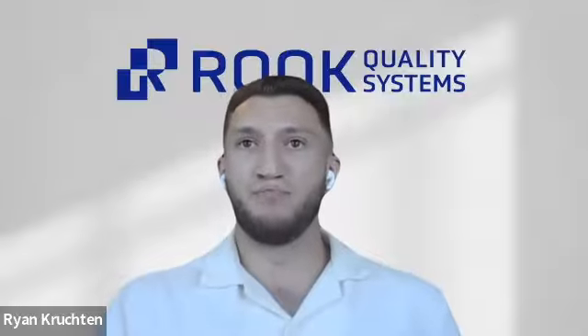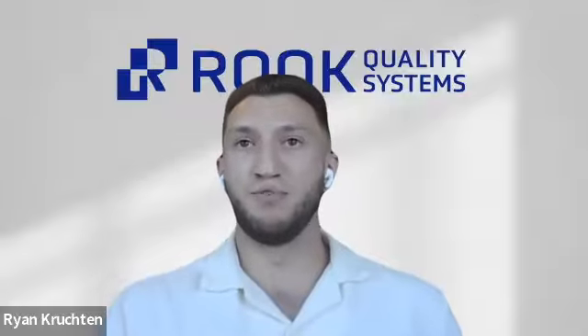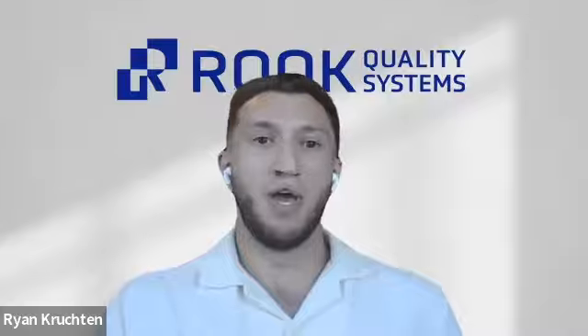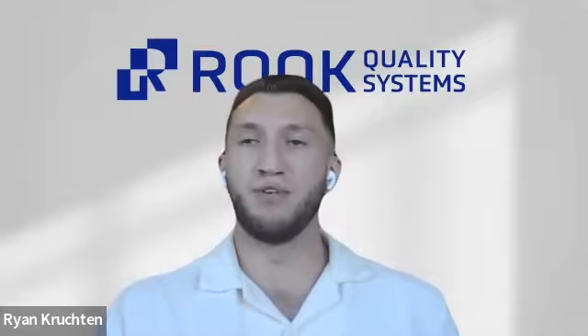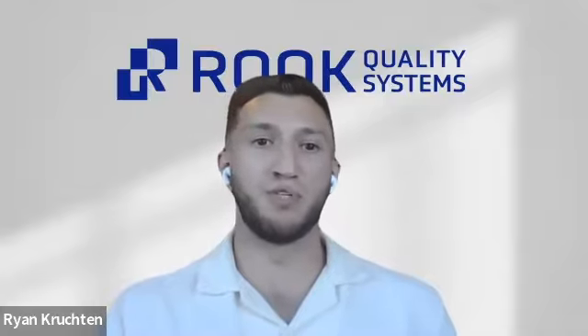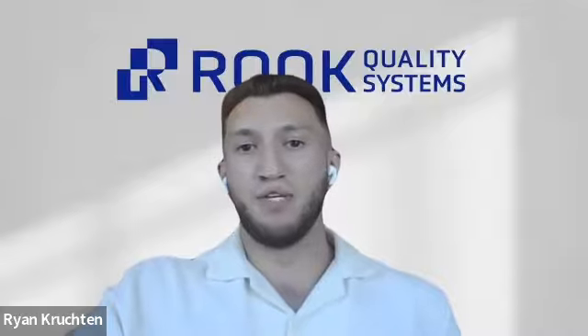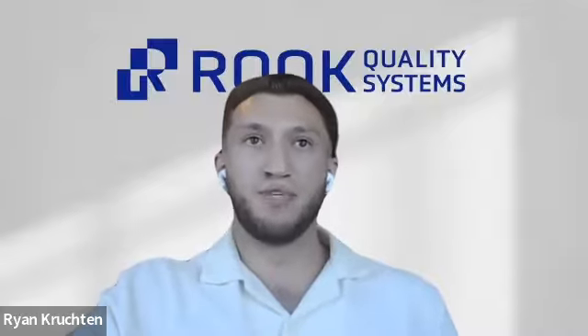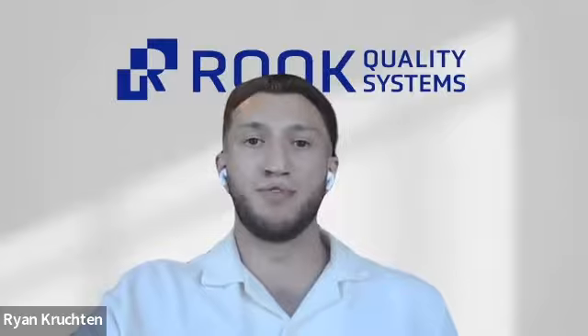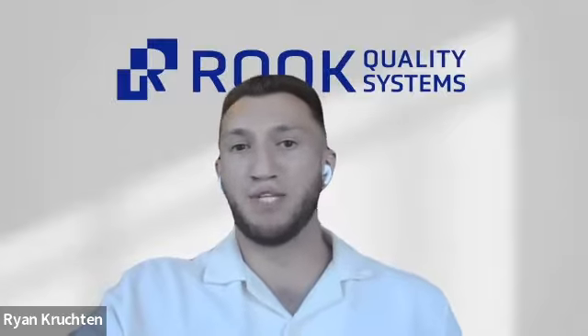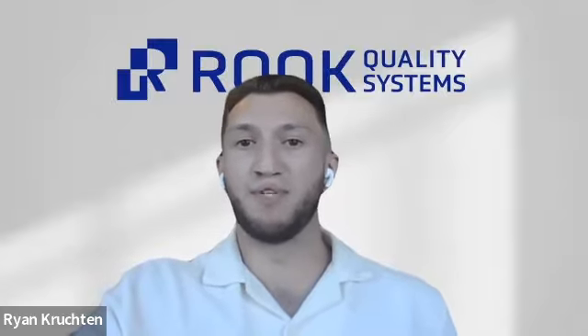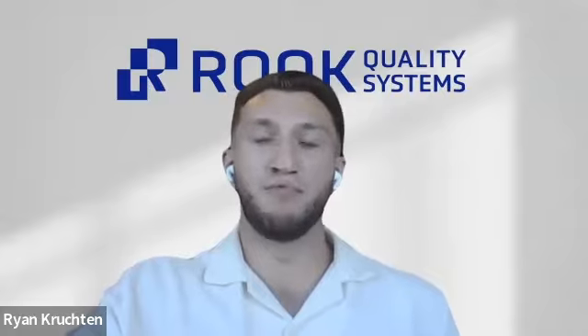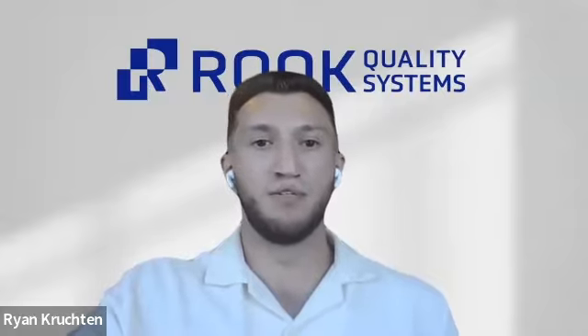It's a proactive way to future-proof AI products, reduce your regulatory burden down the road, and increase transparency with the FDA so they feel comfortable with what's going on and what changes are being made. The key is that the FDA gets the chance to review this PCCP prior to market clearance or approval. And that's evidenced by the PCCP having its own field in the E-Star template for 510K submission.